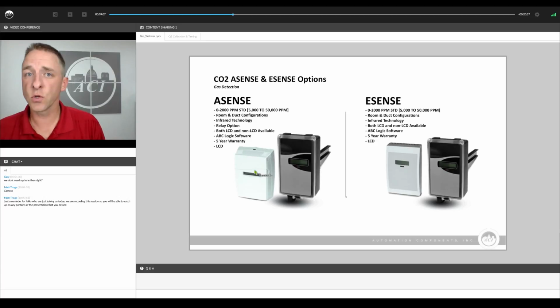On these units, you have the ability to change the range from 0 to 2,000 to 0 to 5,000 or beyond. The CO2 R2 that we talked about in the previous slide is fixed at a 0 to 2,000 parts per million range, whereas these two options give you the ability to change the range for more industrial sources of CO2.